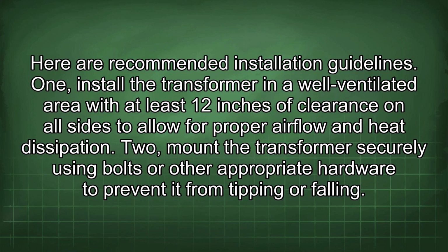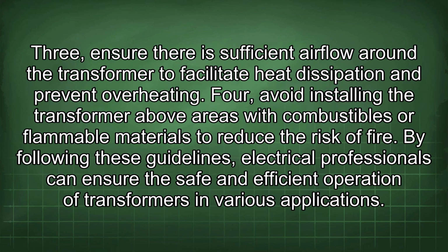1. Install the transformer in a well-ventilated area with at least 12 inches of clearance on all sides to allow for proper airflow and heat dissipation. 2. Mount the transformer securely using bolts or other appropriate hardware to prevent it from tipping or falling. 3. Ensure there is sufficient airflow around the transformer to facilitate heat dissipation and prevent overheating. 4. Avoid installing the transformer above areas with combustibles or flammable materials to reduce the risk of fire.